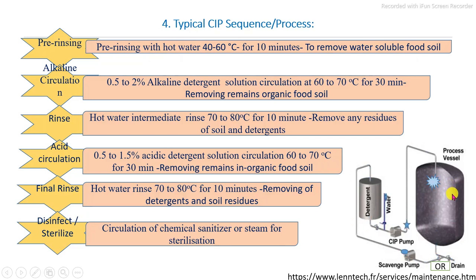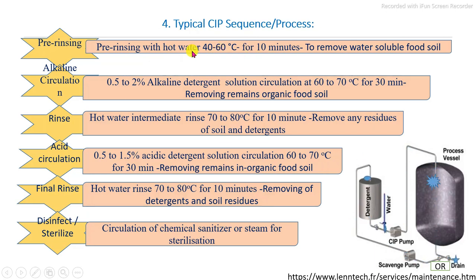In this cleaning process, the first step is the pre-rinsing process with hot water, which is circulated through the processing vessels or the processing line at 40 to 60 degrees Celsius for 10 minutes continuously, to remove the maximum amount of food soil.